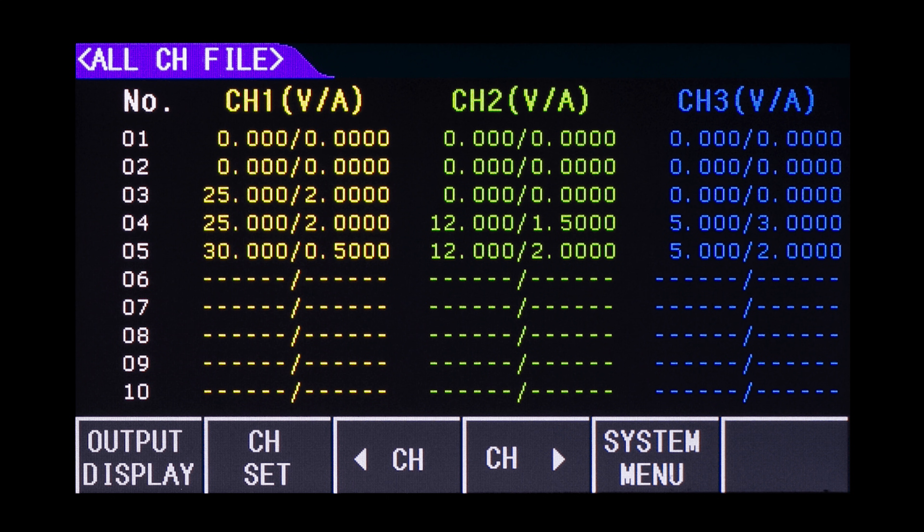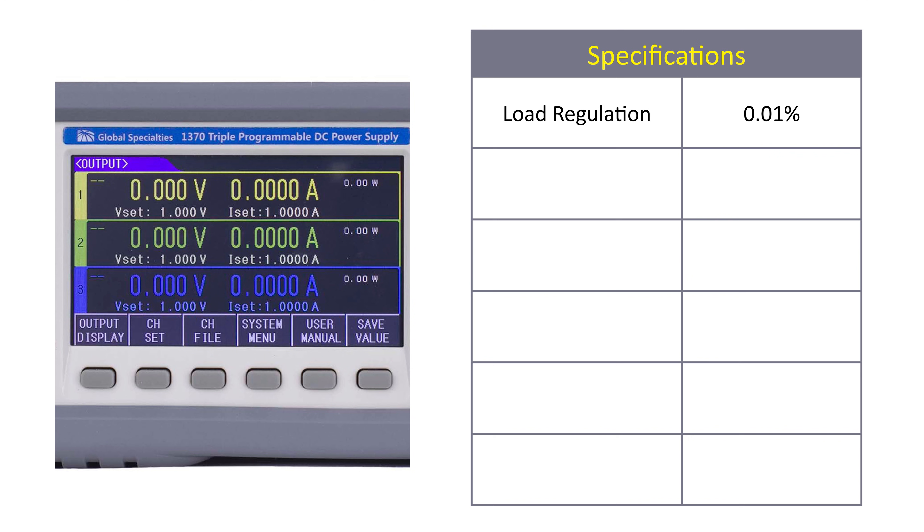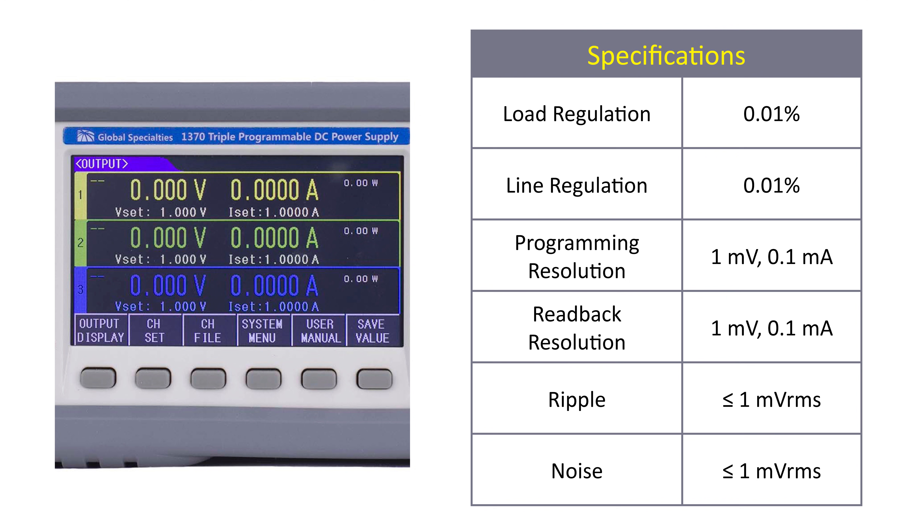The series features both over voltage and over current protections. All models in the Performance Series feature excellent load and line regulation at 0.01%, and programming and read back resolutions of 1 millivolt and 0.1 milliamp.